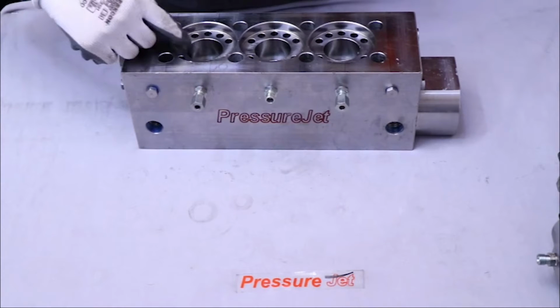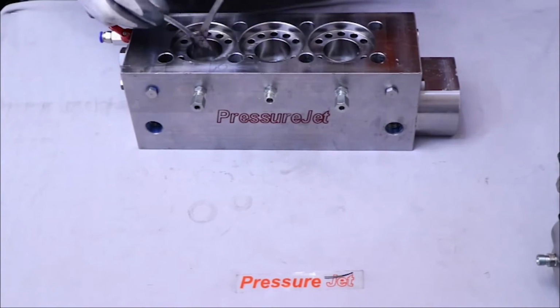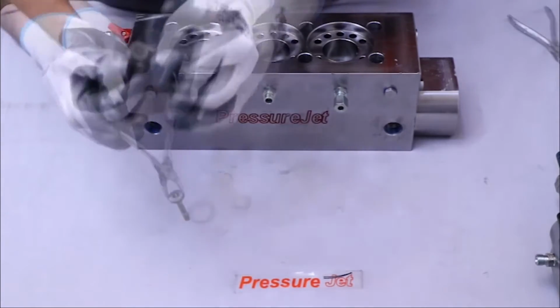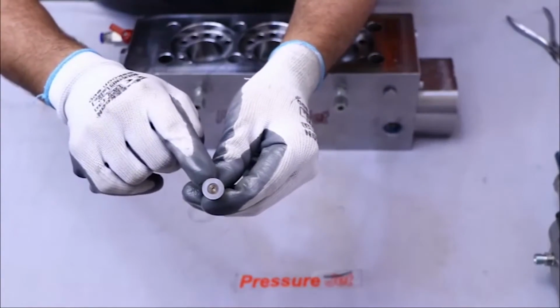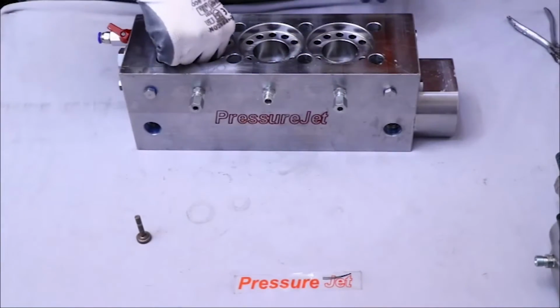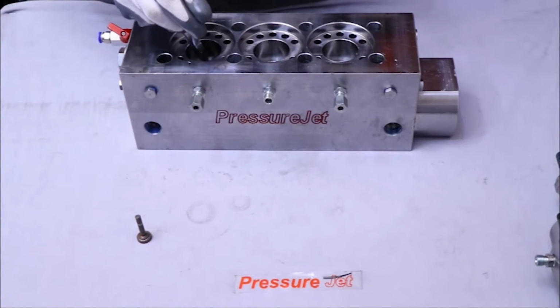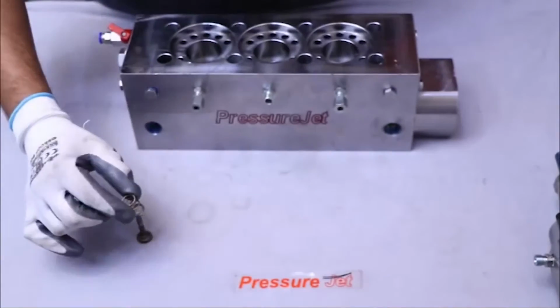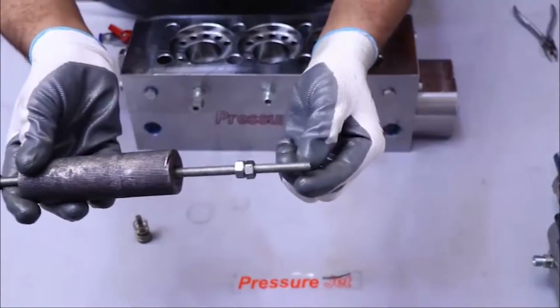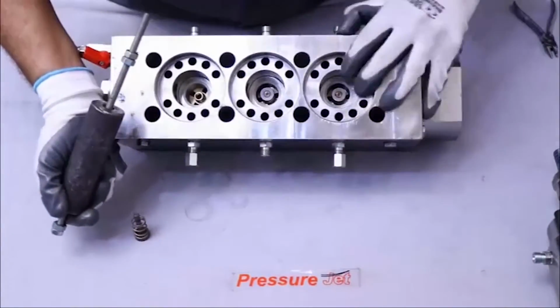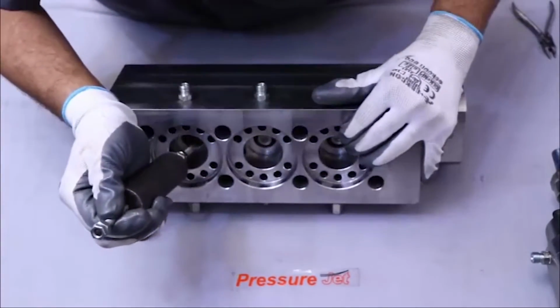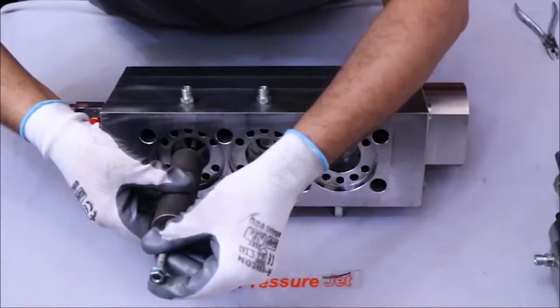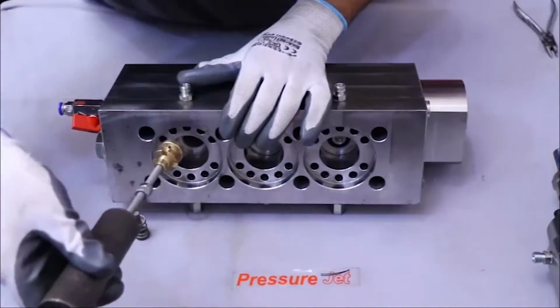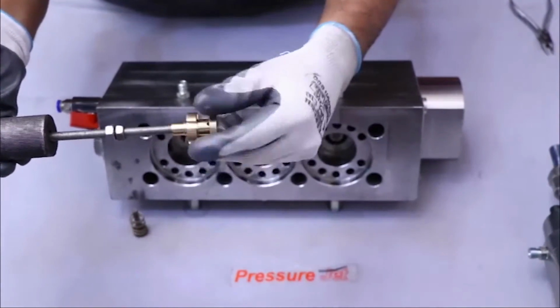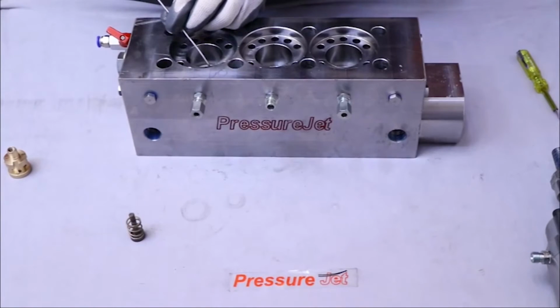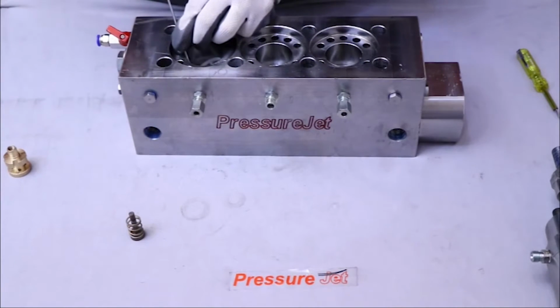Now, we will disassemble the discharge valve. Take circlip pliers and gently take out the discharge valve without damaging its surface. If any scratches are found, then replace it with a new one. Then remove the helical spring using circlip pliers or manually. Take the discharge valve guide puller and screw its threads into the discharge valve guide. Disassemble the discharge valve guide with the help of the discharge valve guide puller. After that, remove the POM gasket using a pick or screwdriver.